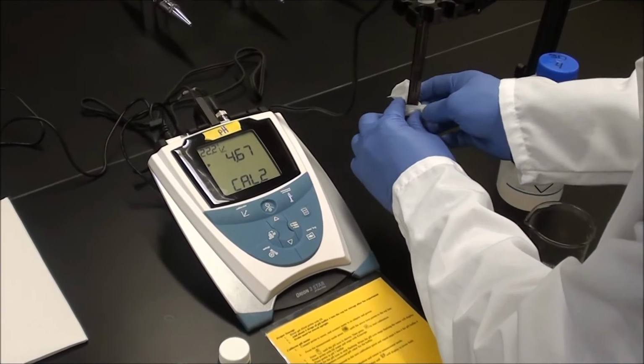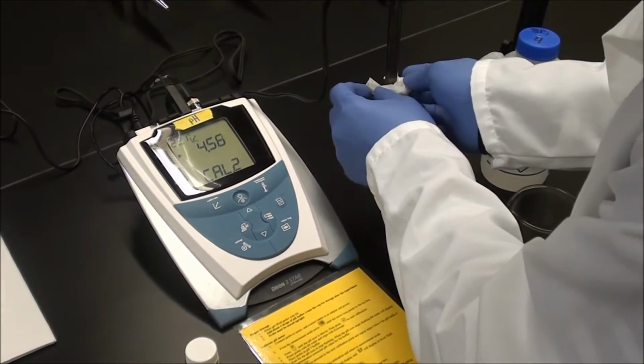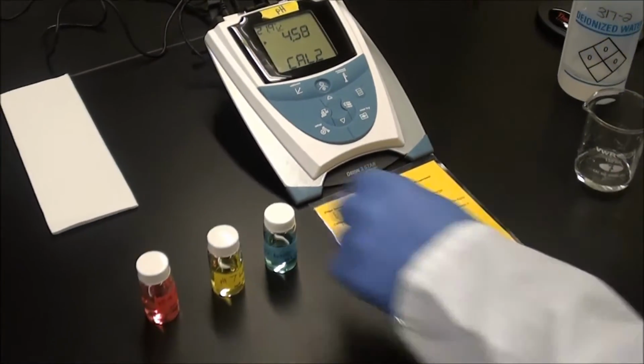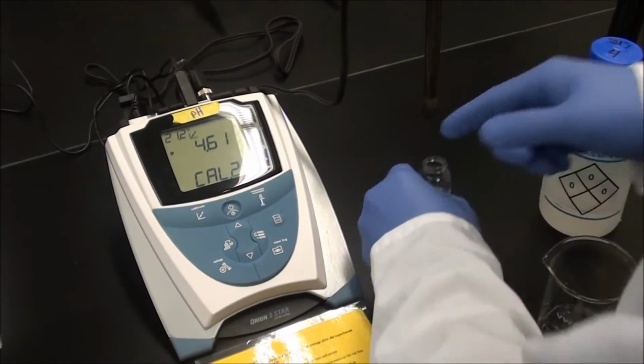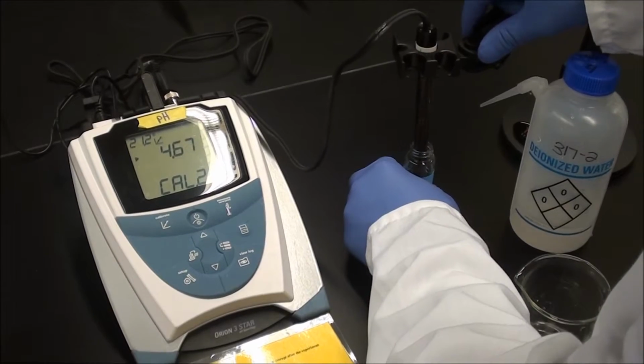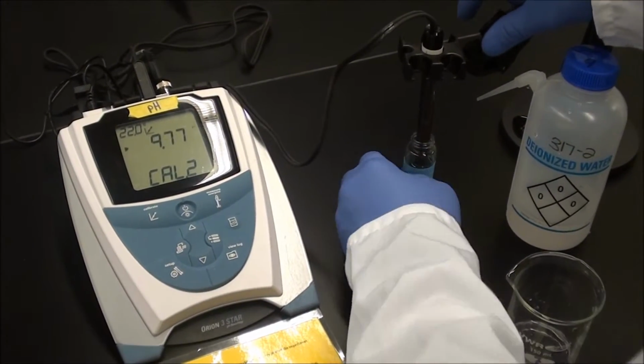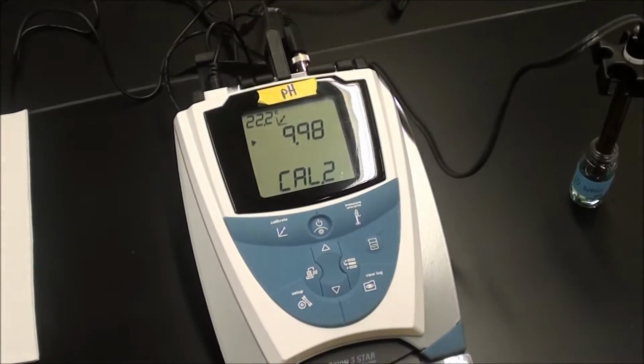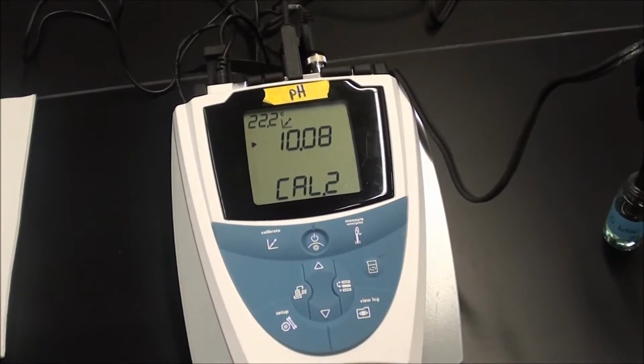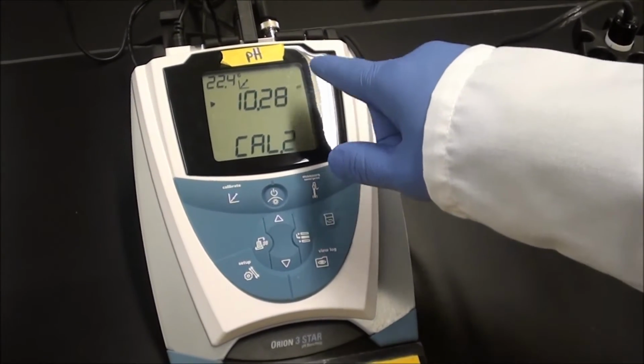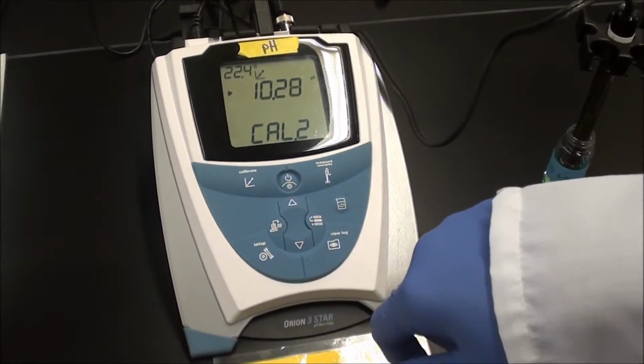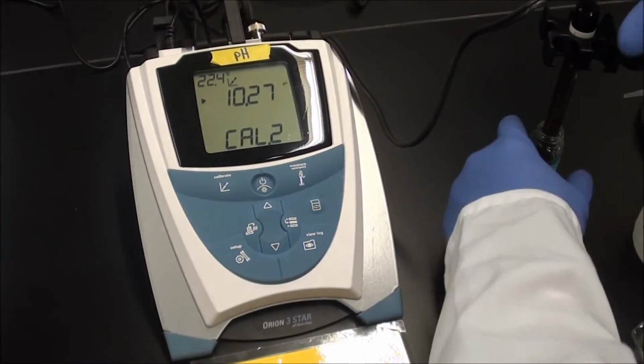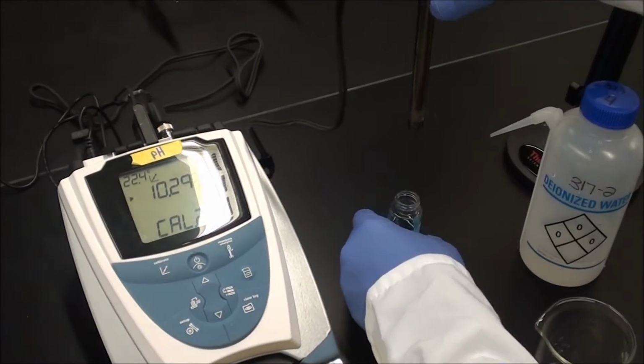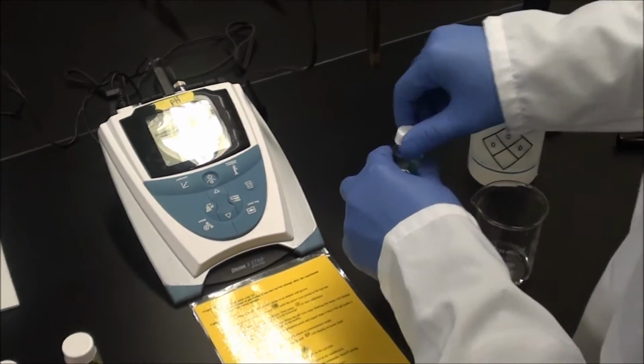And we're going to proceed to the next point, at which we're going to be using the pH colored buffer 10. Set it underneath, submerge it all the way down, and you wait until the pH icon stops flashing again. So it looks like the icon on the pH stopped flashing, so we're gonna go ahead and push the calibration button once again. So it's calibrating. You take out the pH probe from the pH buffer 10. Want to go ahead and rinse that again with the DI water.